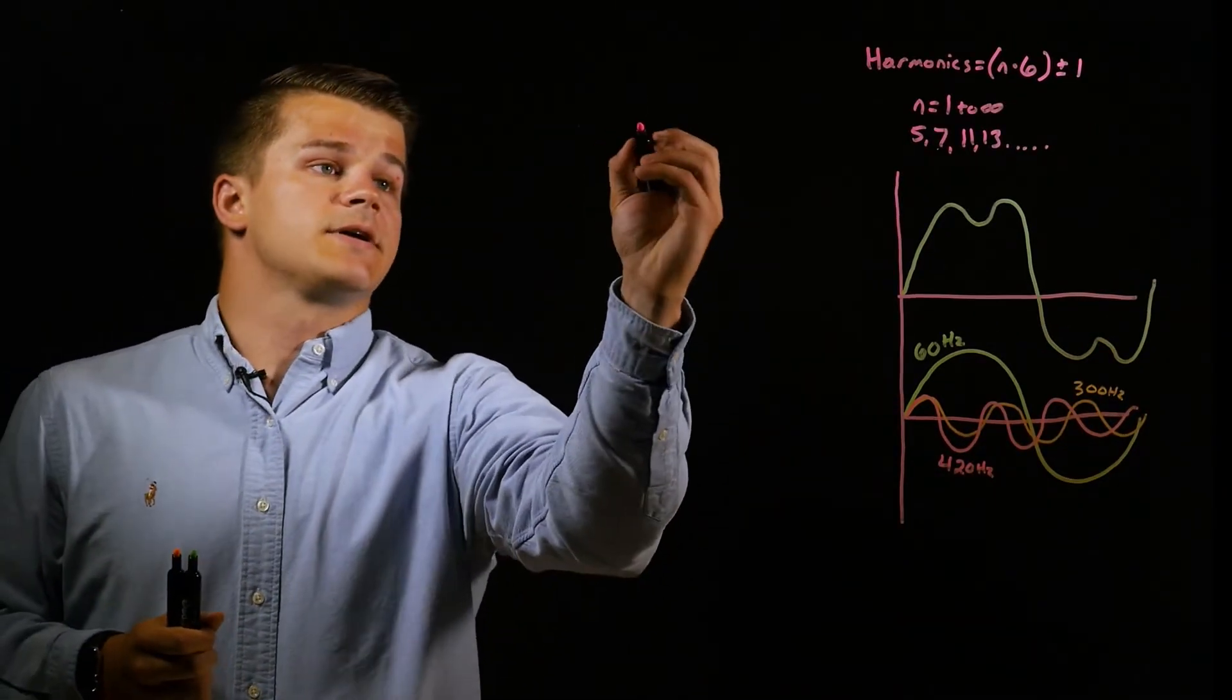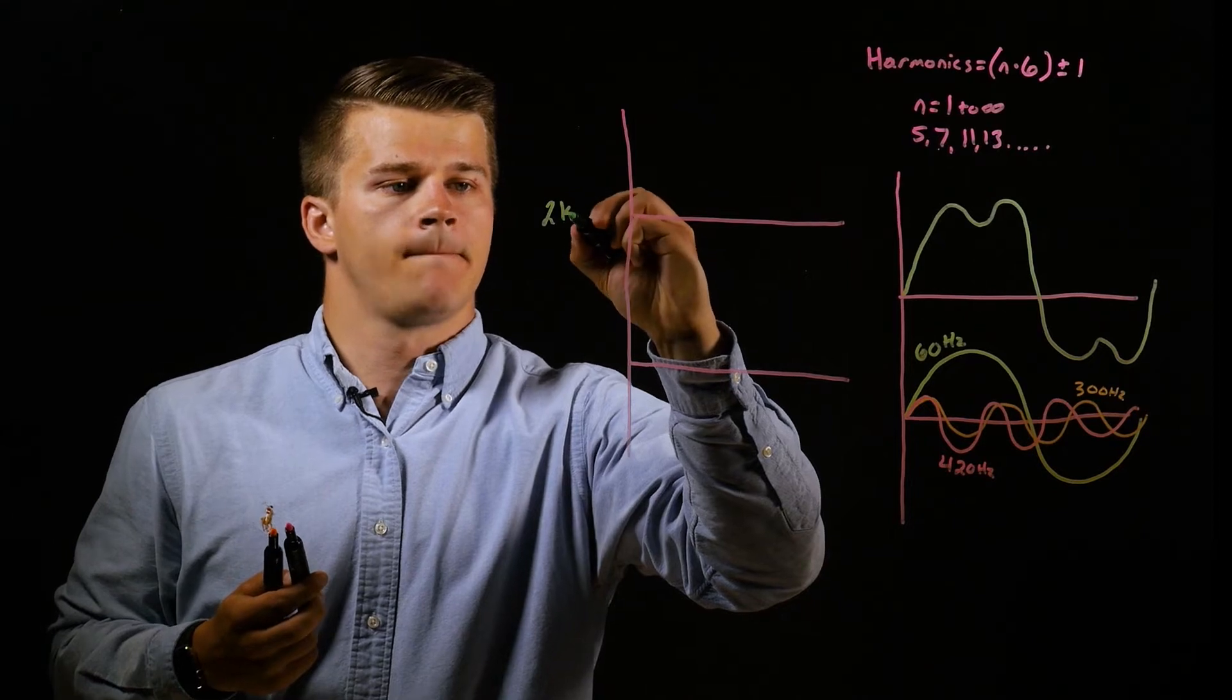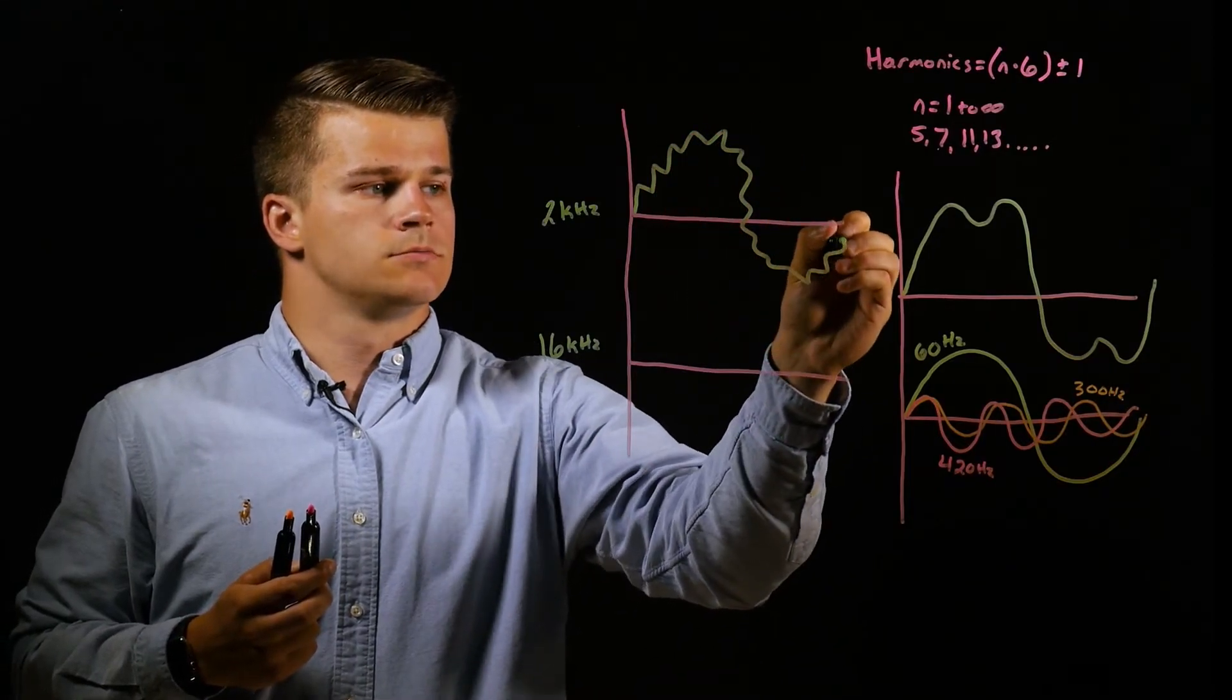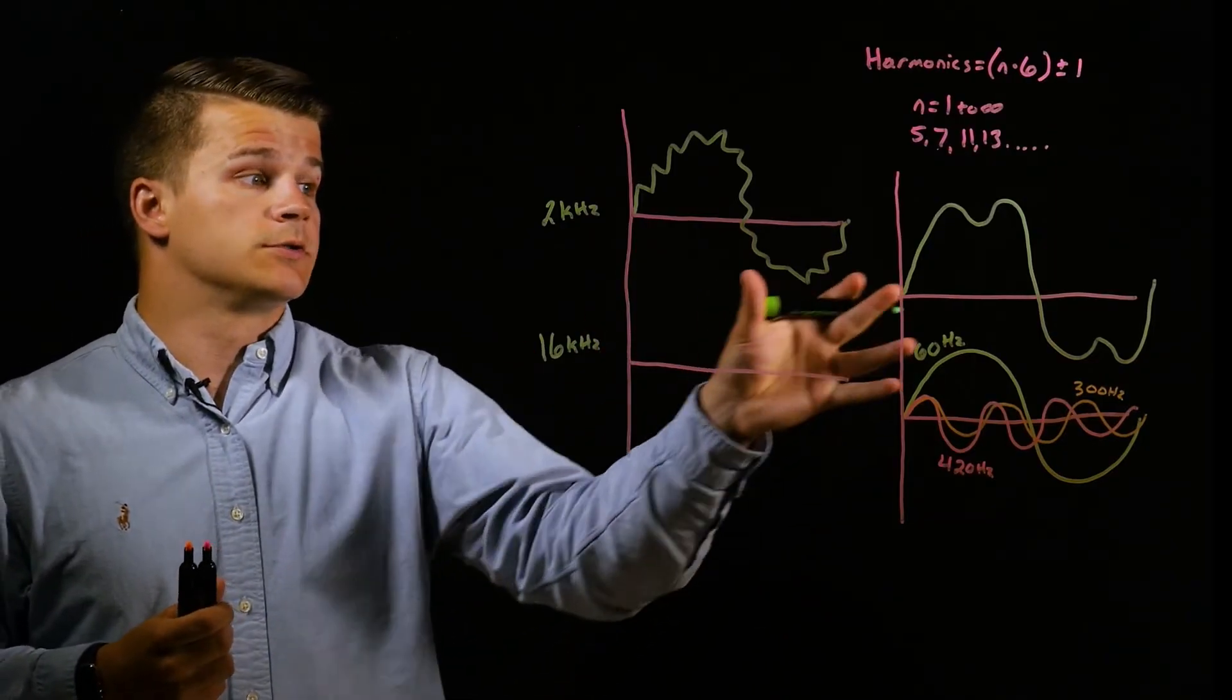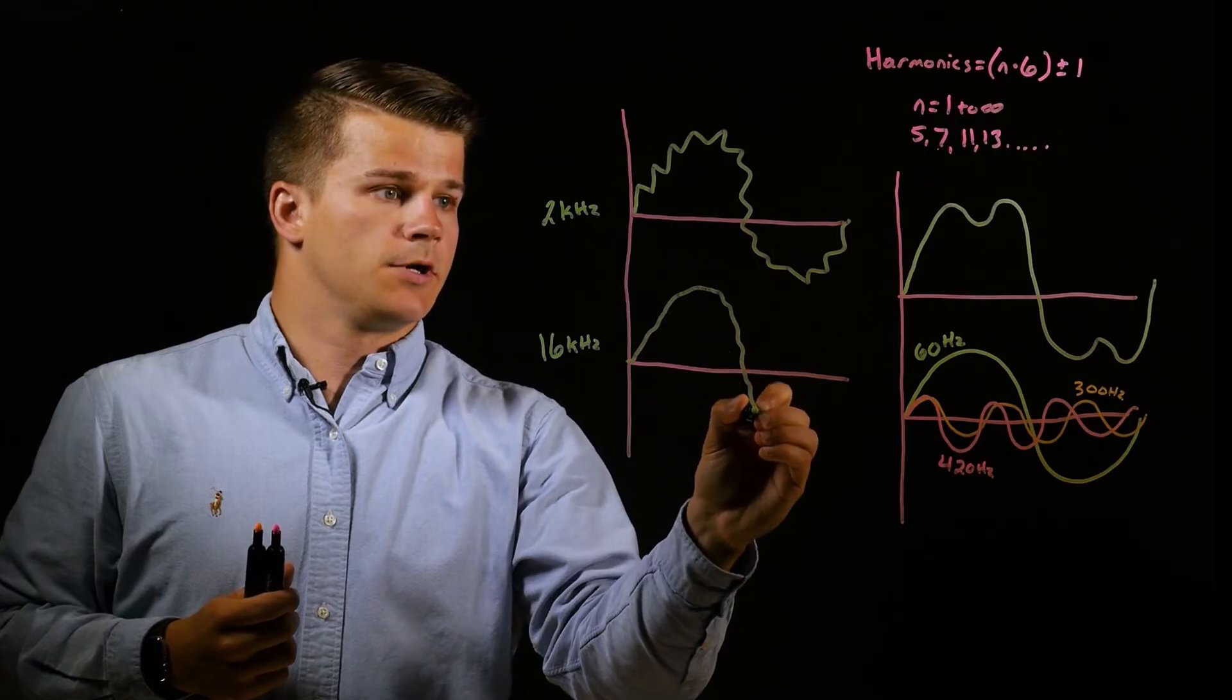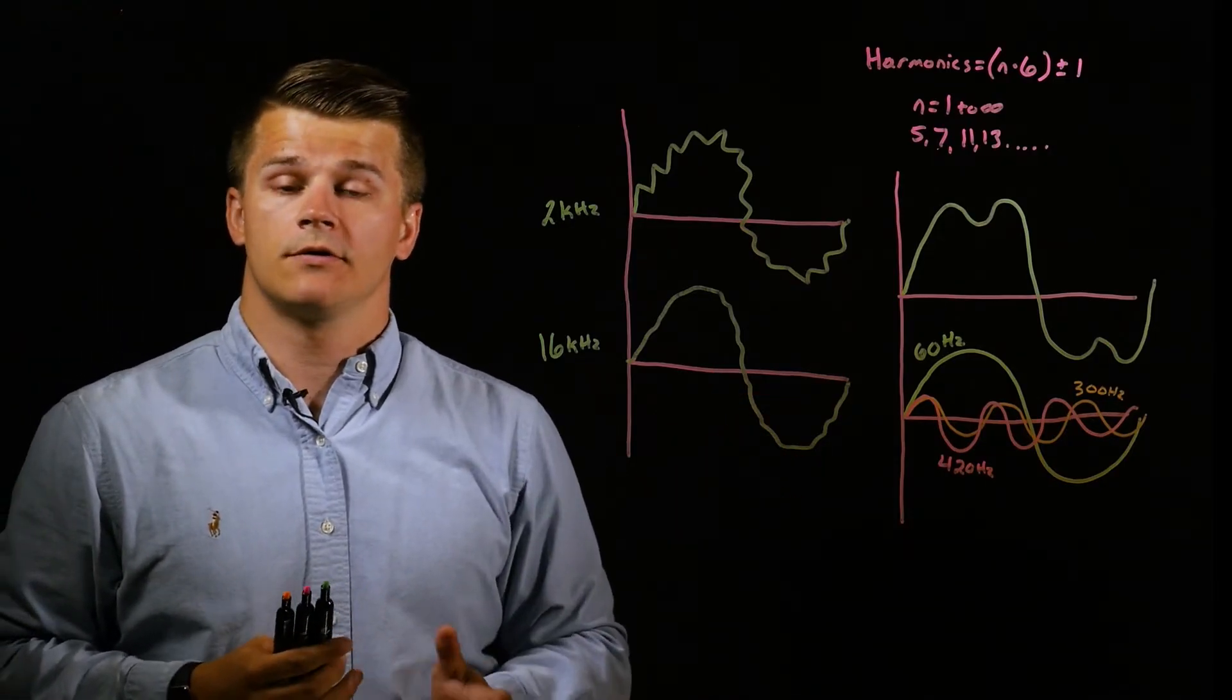The effect that has on the harmonics is if we draw one more graph, we'll say for example, if this is 2 kilohertz and this one is 16 kilohertz, you'll have high harmonic distortion with a lower switching frequency. And as your switching frequency increases, you'll decrease your harmonic content and get closer to a true sine wave. It won't be a perfect sine wave with the PWM, but it'll be much closer as the switching frequency increases. And this effect is more pronounced as the output frequency to the motor increases.